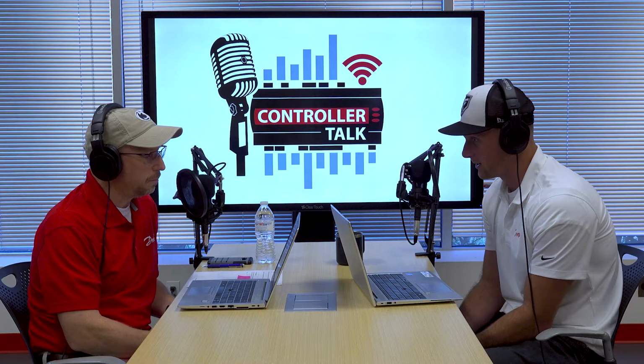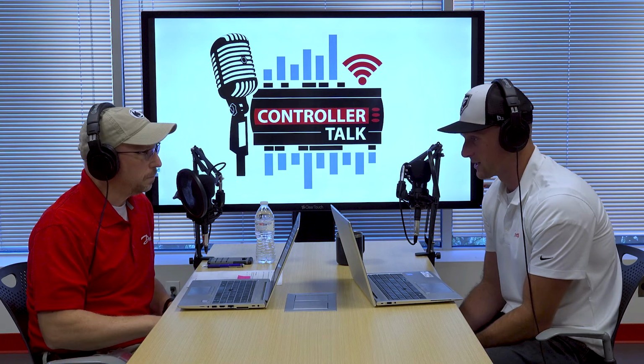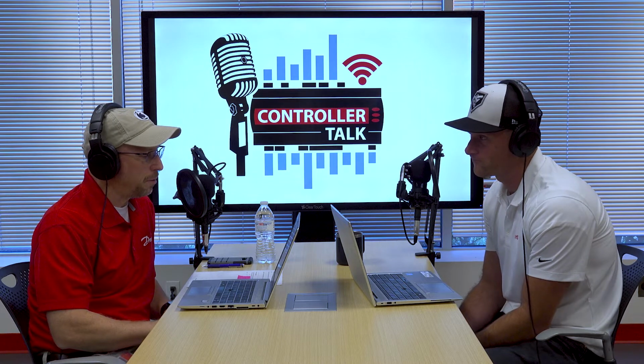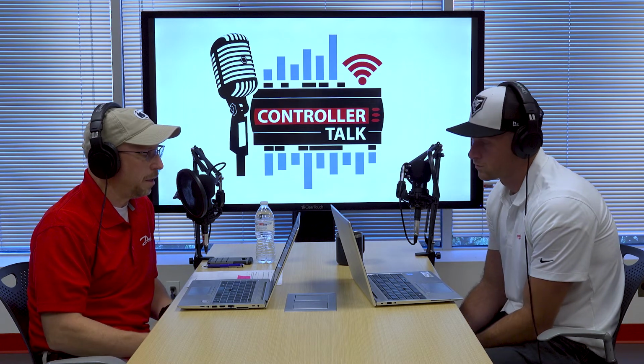Right. So maybe this is a conversation you have with us of, can I upgrade them all to the latest version if that's what you're looking at? But in general, you want to have them all at the same version as a best practice. Right. Sometimes it can't be helped if you have to change something out at the last minute, but we've seen issues where you upgrade unit 1, but unit 0 is older, and then unit 1 won't send its alarms out. Or host comm problems is something I've seen stem from that too. Yep. So that kind of addresses the question of the 255. But you're right, if there's a question about here's my situation, what should I do, then they can always get a hold of us. Yeah, exactly. Yep. All right.